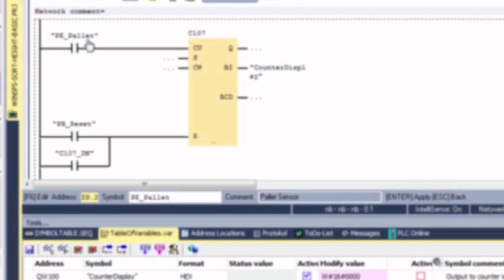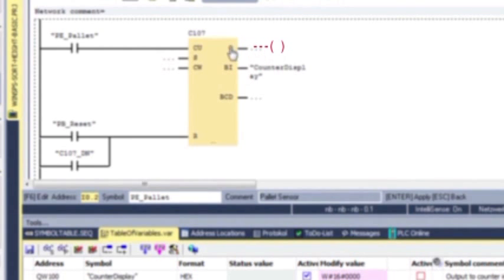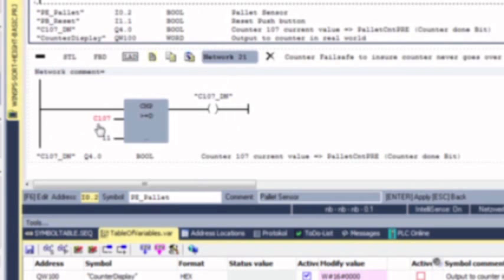In other words, a photo eye detects each pallet released and then increments the counter up. Over here is a place where we could have put an output bit that indicates the counter is counting, but more useful would be a counter done bit. Like an Allen Bradley PLC, you would have an output for counter done — but the Siemens PLC doesn't have that. We'll create another rung below this one that will have a comparative statement to create our own counter done bit.